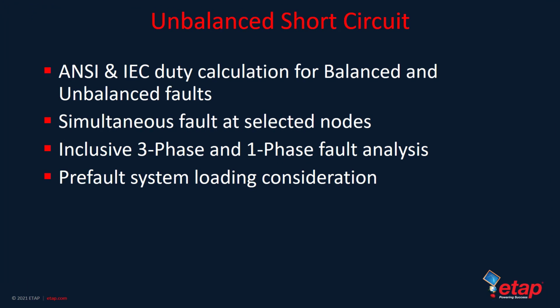So continuing on with the types of studies that are available is unbalanced short circuit. This study type accurately models unbalanced networks, especially untransposed lines and unbalanced shunt devices and sources. Also, it'll do a simulation, series compensate lines, simulate simultaneous faults. So if you have multiple circuits on the same pole, you can simulate simultaneous faults on that, and also you can perform study faults at several locations.